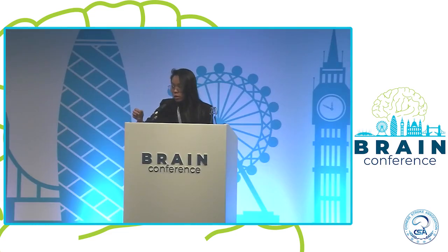Thank you for your question. We chose 800 cc because it's the common setup for in-vitro experiments in the literature, but there's also another factor: our 3D model is not compliant enough to simulate both the systolic and diastolic pressures. So to compensate for the lack of realistic pressure, we increased the flow a little bit.